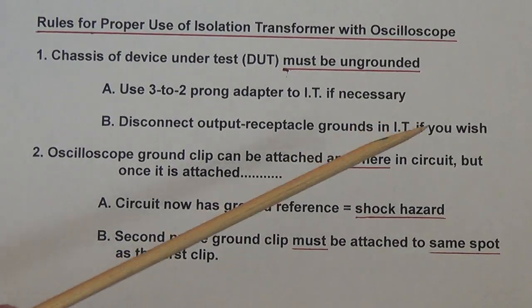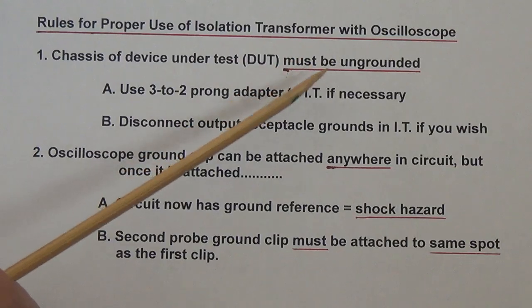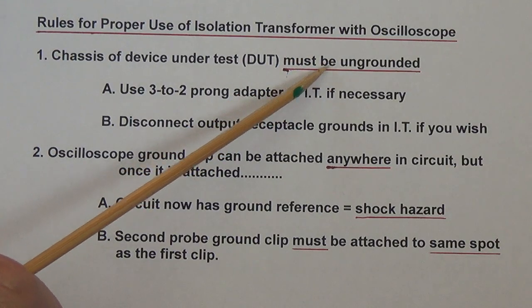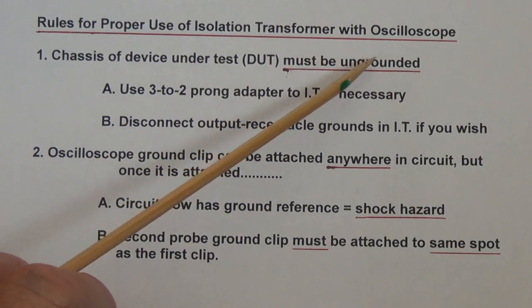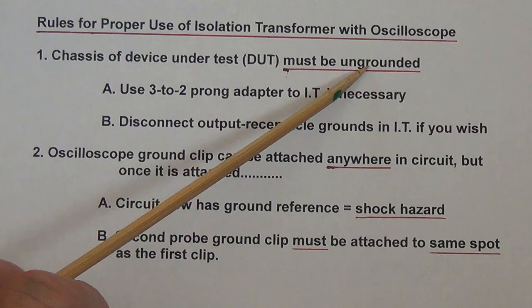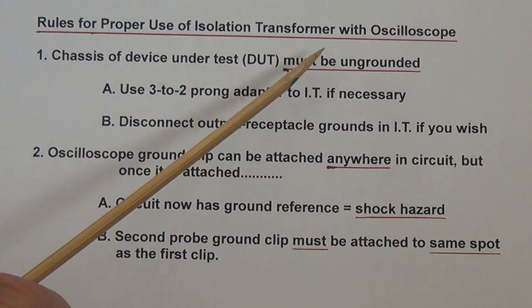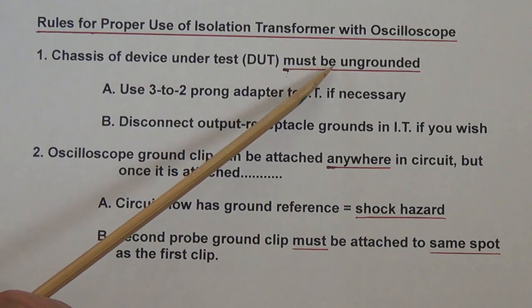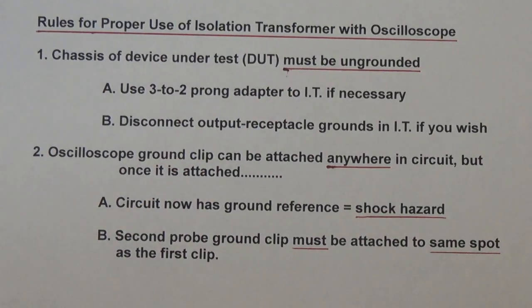Now, this was well demonstrated in the video where I showed you that with an ungrounded chassis, none of the points within the circuit had any potential to earth ground, and therefore could not harm your oscilloscope or probes. The minute that a ground was provided to the chassis, all that changed, and the circuit went back to having all of its normal operating voltages and presenting once again a very serious hazard to both you and the oscilloscope and probes.